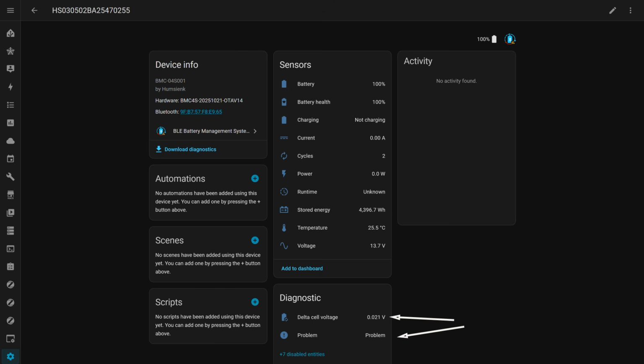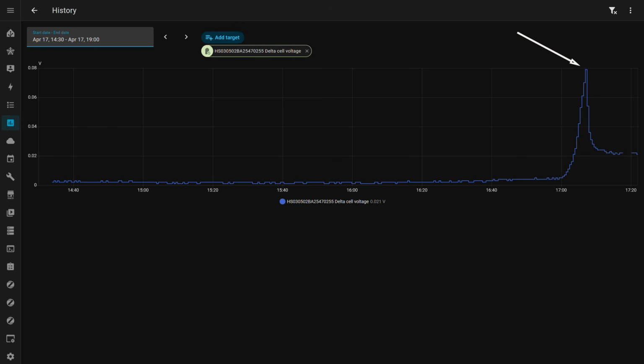What do we see here? The stored energy reading decreased slightly, by about 40 watt-hours, and the voltage is 13.7 volts. But the cell delta rose above 20 millivolts, which caused the problem sensor to trigger. Moreover, as can be seen from the graph, at the end of charging there was a sharp peak up to 80 millivolts, followed by a drop to 21, which is still above normal, as the problem sensor shows.